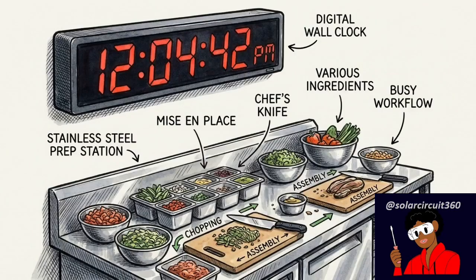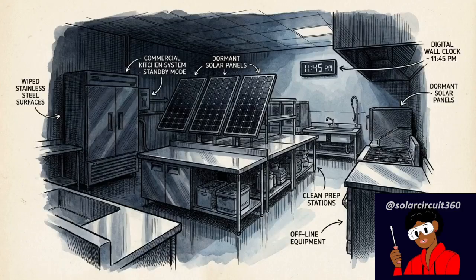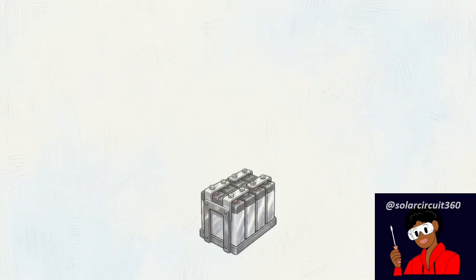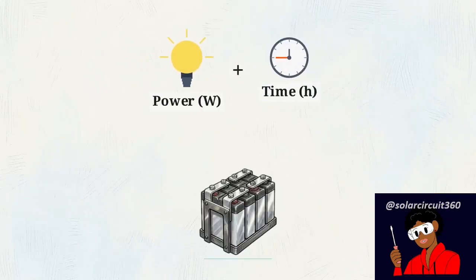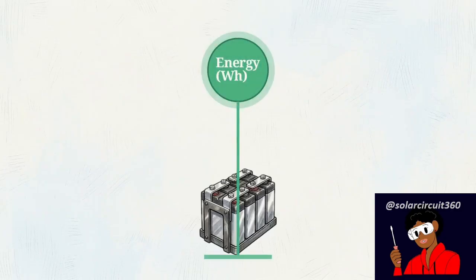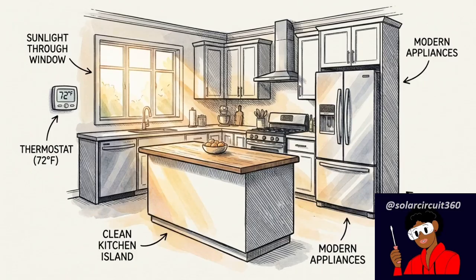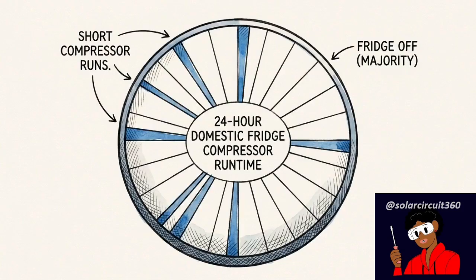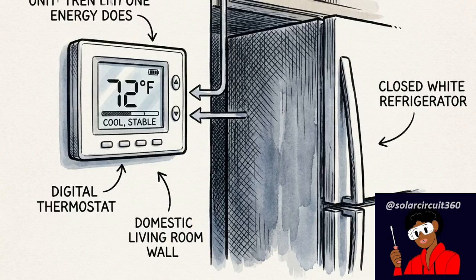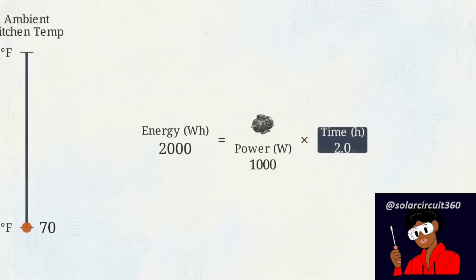Managing instantaneous power spikes keeps the system online minute by minute, but surviving an entire operational day requires calculating total energy storage accurately. This formula dictates the required size of the battery bank. Energy in watt-hours equals power multiplied by time. In a climate-controlled house, the time variable is predictable. A domestic fridge compressor only runs a few hours a day because the ambient temperature is comfortable and the doors remain closed. A commercial kitchen operates near 100 degrees Fahrenheit during peak dinner service.